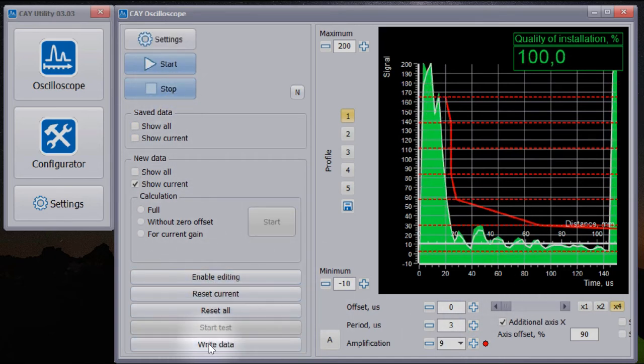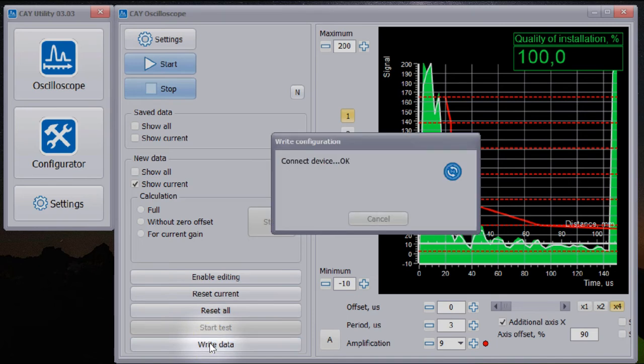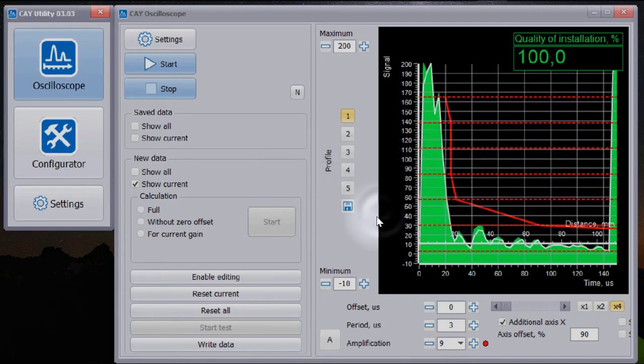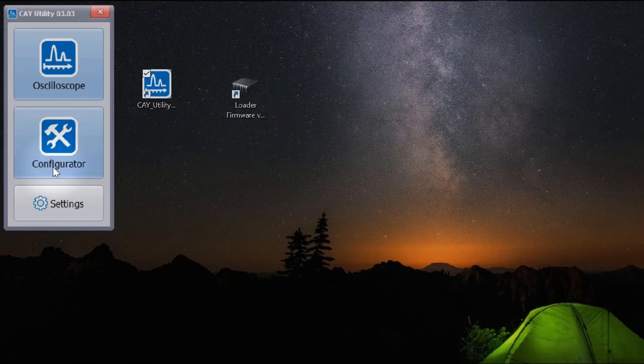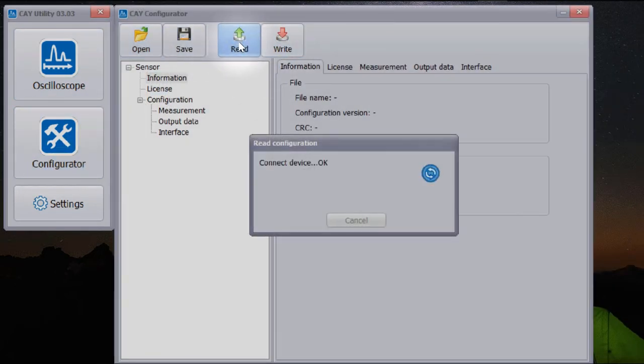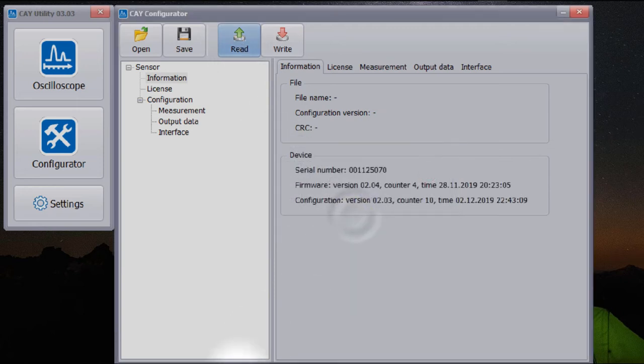After finishing, we exit the edit mode. Stop the sensor and write the configuration to the sensor. Then we go to the configuration utility. Reading sensor data. We can see the serial number of the sensor, the firmware version with the latest date of sensor update, and the firmware update counter. Also, the version of sensor configuration, its date, and the sensor configuration counter.